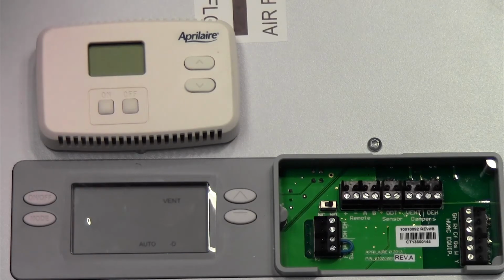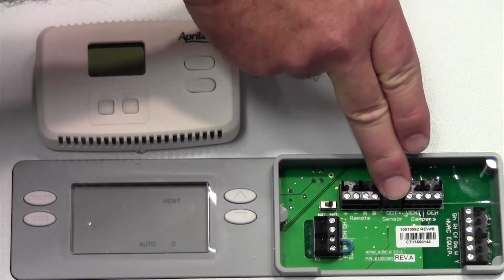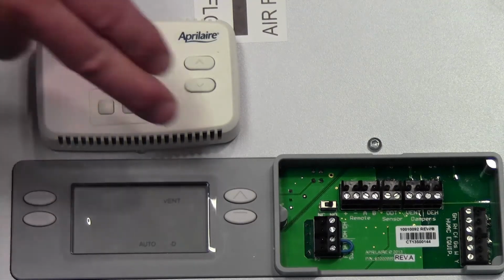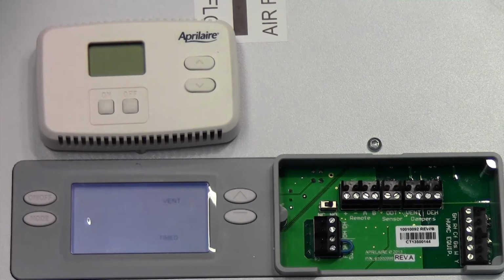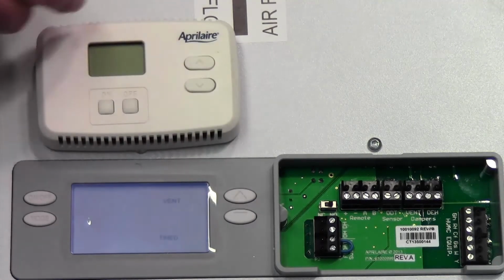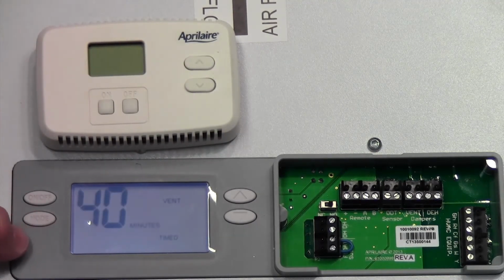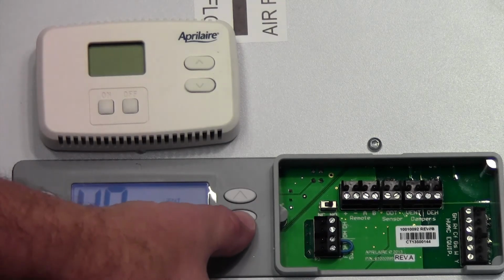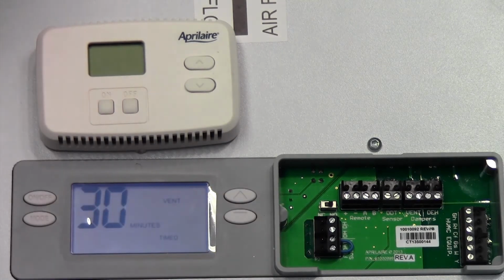The vent B, C, and D give us outdoor temperature parameters, so if it's too hot or too cold, we will not ventilate. And when doing that, we'll come over here and we'll tie in an outdoor temperature sensor to this control, so we'll know what that outdoor temperature is. So we can select that, or again, we can just have it be vent timed if we want to follow more of an ASHRAE type standard. So I'm going to leave it as vent timed. It's going to ask me how many minutes of ventilation, and I can adjust that up and down all the way up to 60 minutes, and that's how much ventilation we're going to provide per hour.